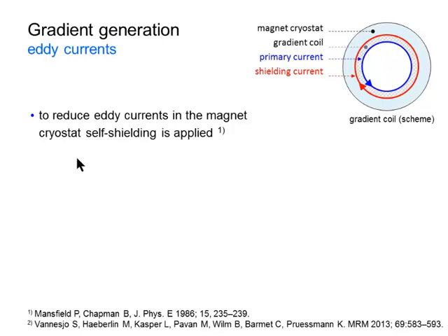Actually, a gradient coil consists of 2 gradient coils using the self-shielding philosophy. The inner coil of this concentric setup is simply generating a field inside the patient, as you might imagine, but also a field that goes into the cryostat, triggering some very long-lasting eddy currents. The outer coil, which is also actually a gradient coil, is counteracting that with the aim to cancel the fields of the inner coil inside the cryostat.